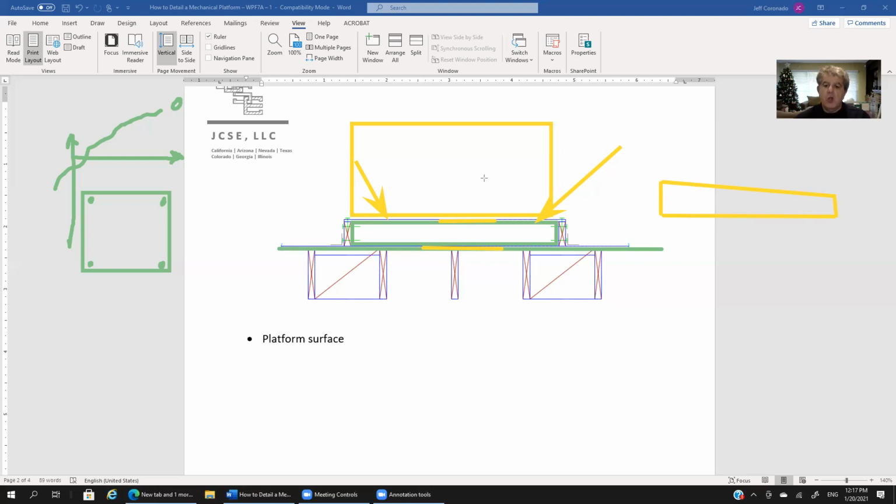Okay, so at the end though, we want a horizontal surface for the sheathing that supports the air handler. We don't want this to be probably anything less than a 2x4. So that's why we start off with a 2x6, because at the end, we don't want this dimension here to be anything less than 4 inches. So in essence, like a 2x4, right? But we don't want it to be less than 4 inches for a couple of reasons.